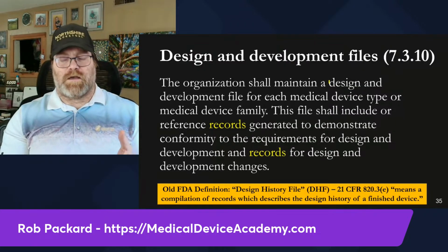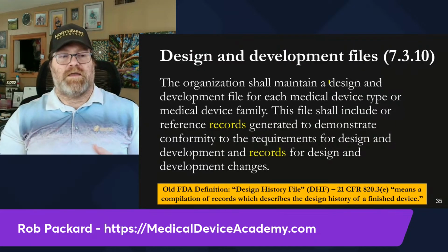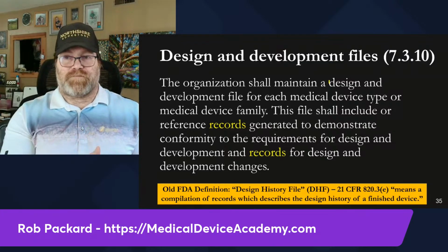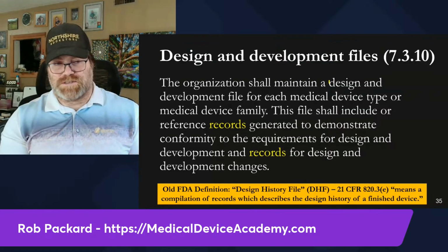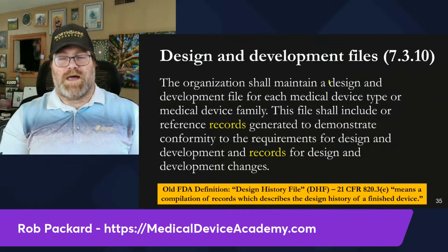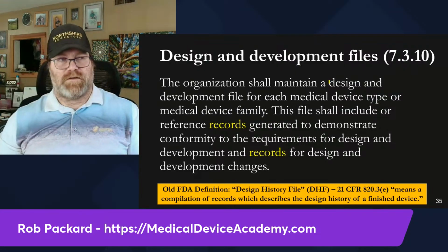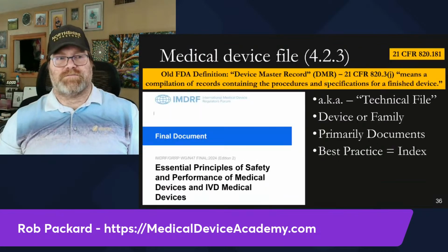That's not the same as your design outputs. They are included in this, but most of the documents are records. They're test protocols that you've approved. They're test reports that you've reviewed and approved. They're verification testing, validation testing. So a lot of records that are in your DHF or design and development files.